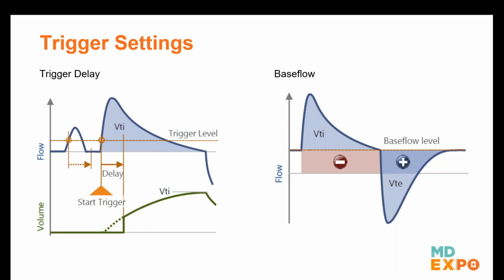The other thing that you will come across is called base flow. A base flow is needed if you have an application where you have an offset of flow of a ventilator that is compensating a leak. For your tidal volumes, this is going to bring it out of balance. So we'll have far higher tidal VTIs and far lower VTEs because of that constant offset of flow. So we can tell the analyzer that offset, and then it's not going to consider that in the volume calculations. But again, this is a little bit more advanced, and in most applications, you will not have to change settings like that on your gas flow analyzer.